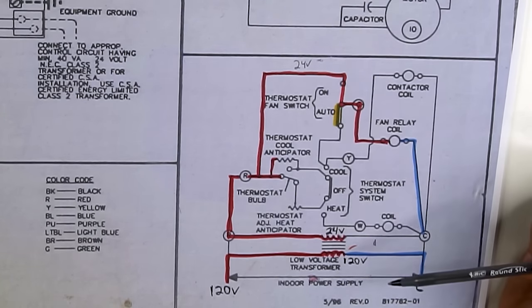Let's go ahead and color our ground green. Now it's properly grounded. Once the compressor is up to speed, this normally closed switch on the potential relay will open up and take the start capacitor out of the circuit. Then only the dual run capacitor stays in until the unit shuts off. That's about it for this wiring diagram — let's go on to our last one.